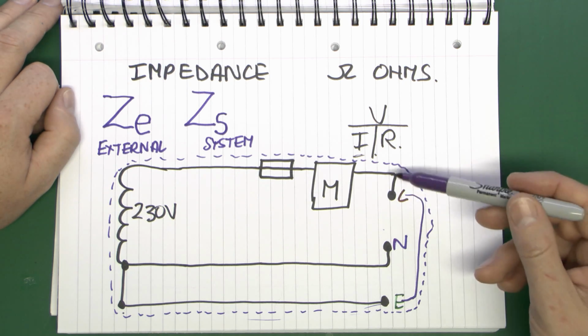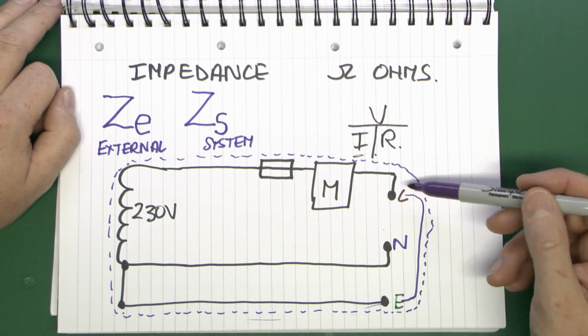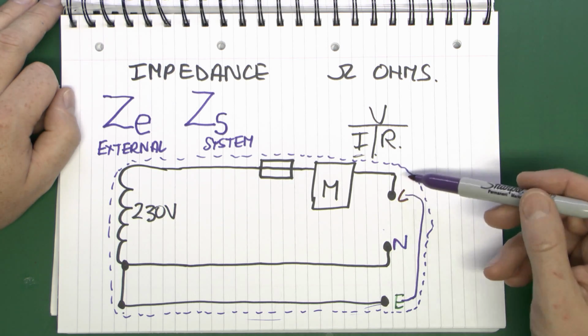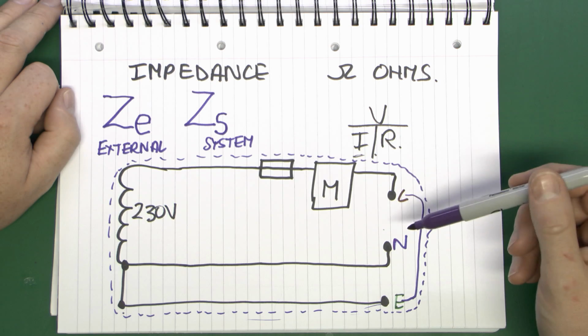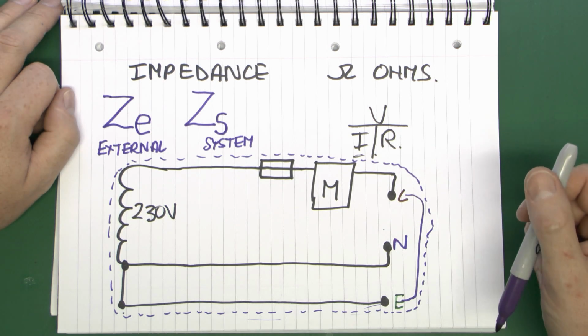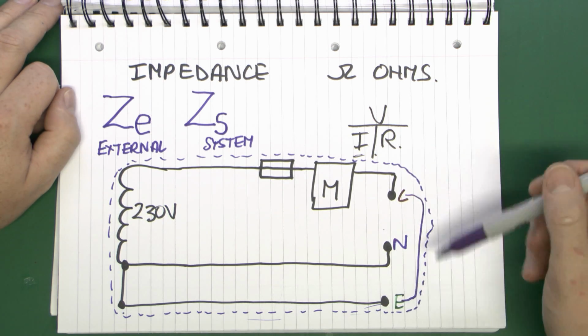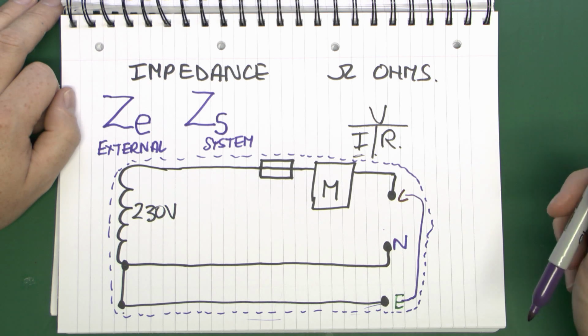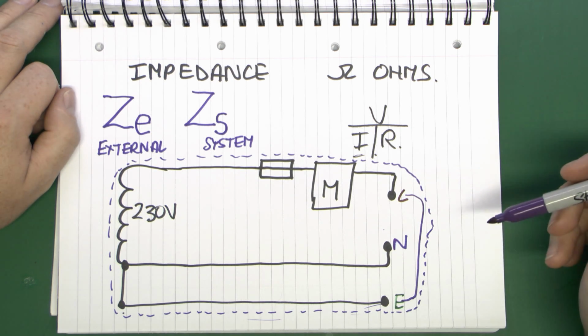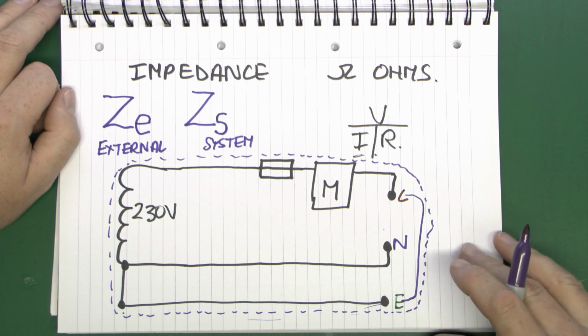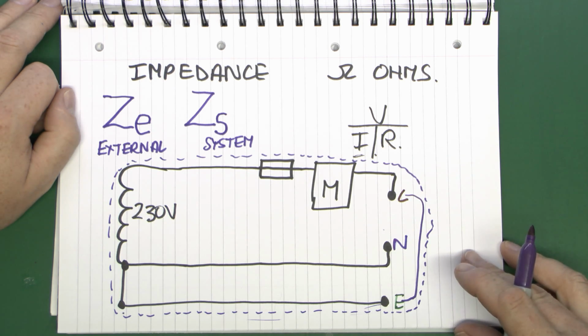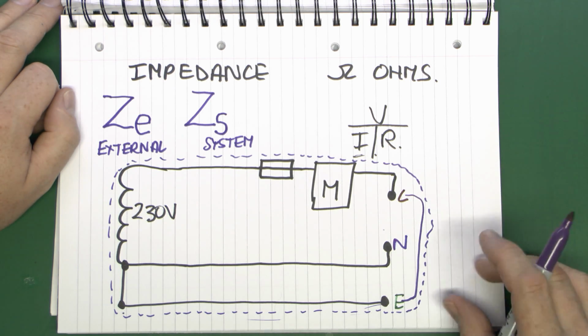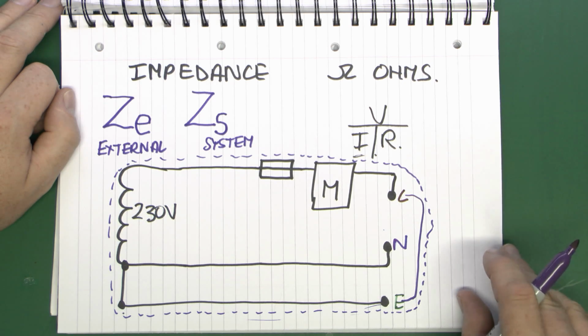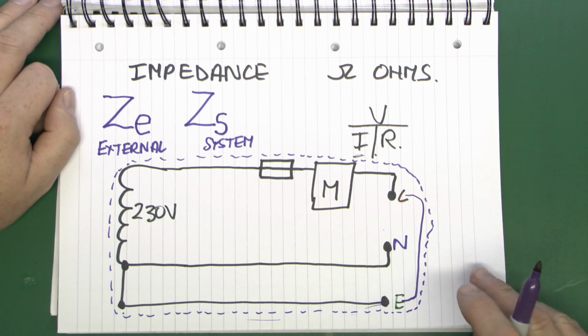The other thing to make sure of is that if you are going to do that, you must use a specific device intended to measure this. You cannot take a multimeter and stick it to resistance range and connect it here, because if you do, the multimeter will blow up in a ball of flames and be destroyed. So this has to be done with a specific piece of equipment designed for the purpose, and that can either be a separate item or, more usually, it's part of one of those multi-function testing devices.